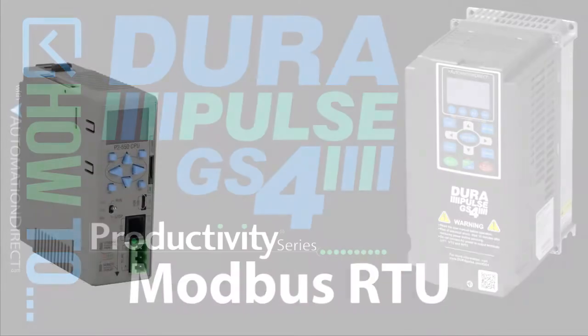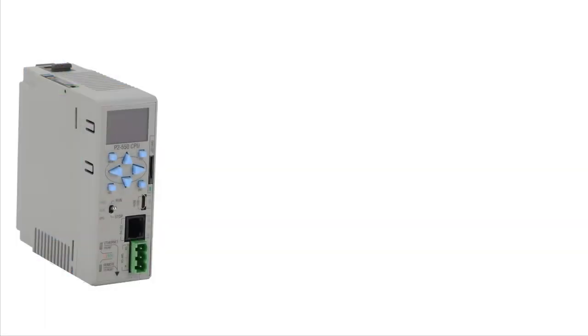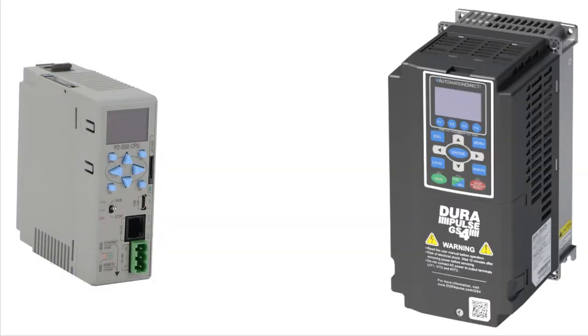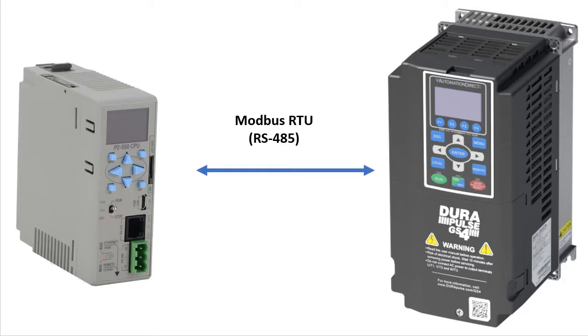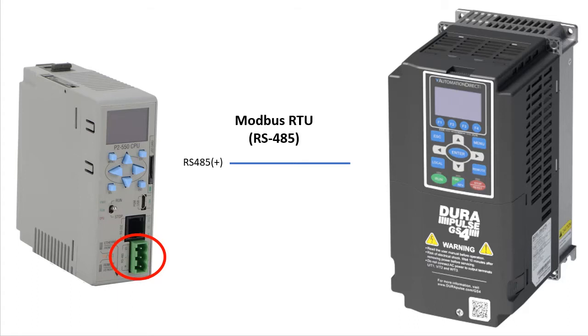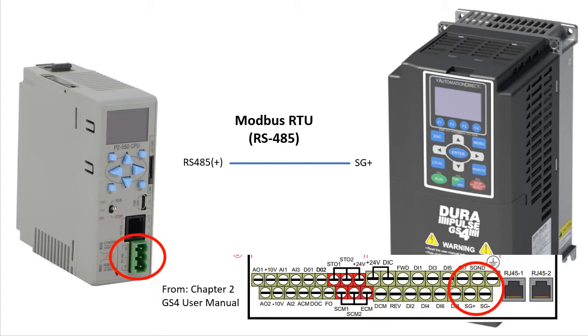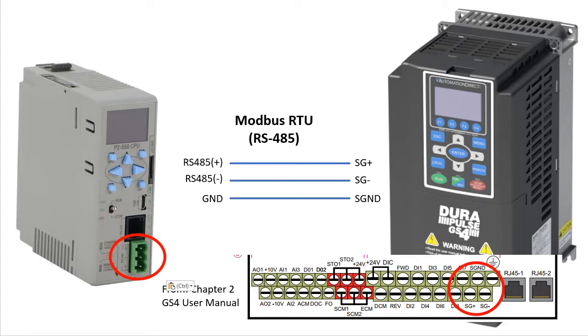We want a Productivity Series controller to control a GS4 variable frequency drive over Modbus RTU. To do that, we just wire the Productivity controller's RS485 plus terminal to the drive's SG plus terminal. And the minus terminal goes to SG minus on the drive and the ground terminal goes to S-Ground on the drive.